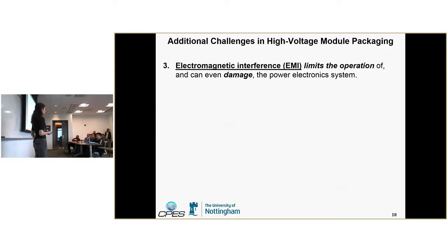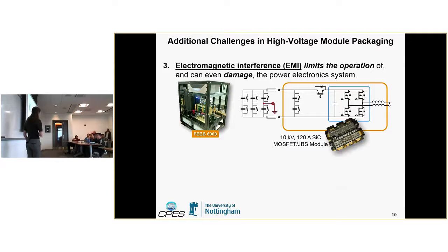And then finally, electromagnetic interference. You do get this in lower voltage as well, but it's also very critical at high voltage. So I mentioned these 10 kV power modules before and how we put them in a PEBB, a power electronics building block. Well, when we went to operate the power electronics building block in a normal converter operation, the maximum voltage they were supposed to operate at was 6 kV. Maximum voltage was limited to less than 3 kV because of significant EMI issues. Actually, all the protection signals were triggering when there was no fault on the system, and even some control components were blowing up.